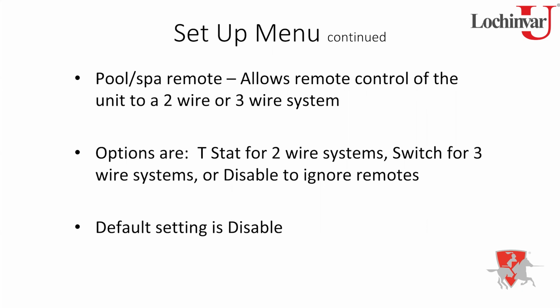Back when I was in tech, this was kind of a common call on startup, or in general, really, because people like to play with controls sometimes. The call was, got an ERN 402, can't get this thing to come out of standby, will not fire. And what it ended up being a lot of times is somebody got in there and played with the control and programmed it to have a 2-wire or switch for a 3-wire system, when in fact they didn't have any type of control wired to it. So it should have been on disable to ignore those other 2 remotes. So keep that in your back pocket too, because that has made people stay on a job site for several hours and replace boards before.